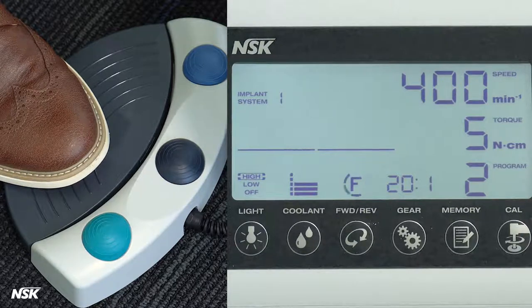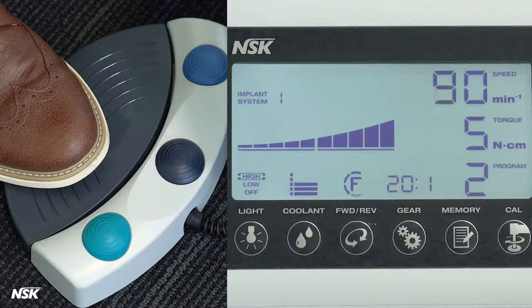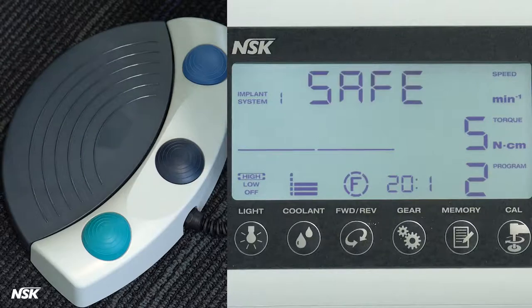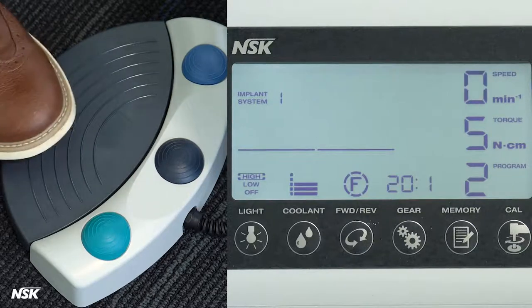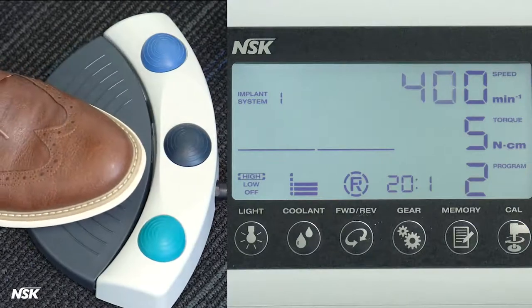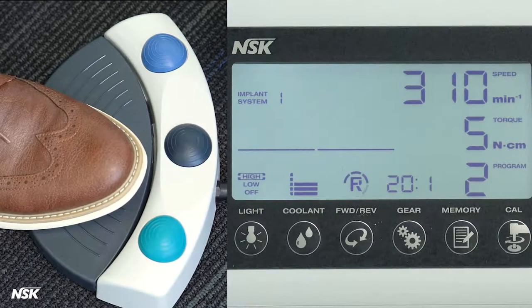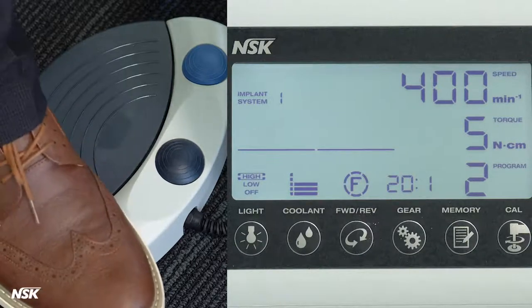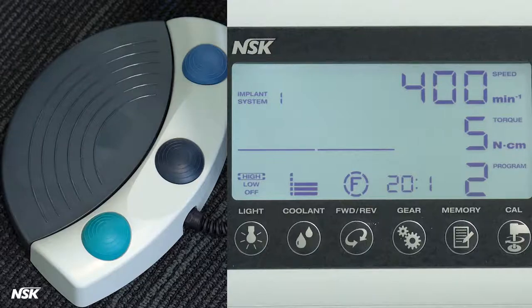If at some point in a procedure a drill becomes stuck in the bone and the torque exceeds the set value in the program, the error message safe will appear on the panel. You will hear a beep and the device will stop. Tap on the speed pedal to clear the error. Then press the green button on the foot control to change the rotational direction and step on the speed control pedal again to release the drill. Don't forget to change the rotational direction back to forward using the touch panel or by pressing the green button again. Now you're ready for another round of drilling.